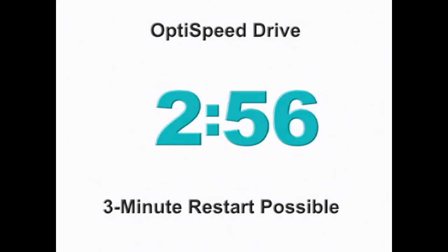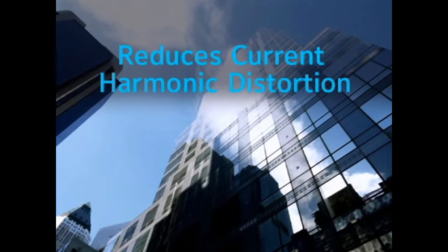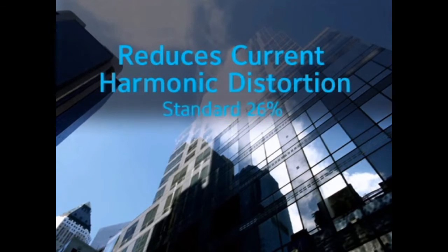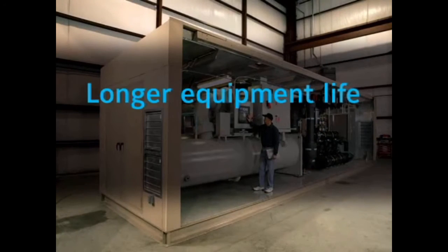For further electrical protection, the OptiSpeed Drive is designed to reduce current harmonic distortion, which can damage other electrical equipment in the building. As a standard, an OptiSpeed Drive reduces distortion to 26%. The available harmonic filter further reduces distortion to meet IEEE standard 519-92. The OptiSpeed Drive will deliver longer equipment life.